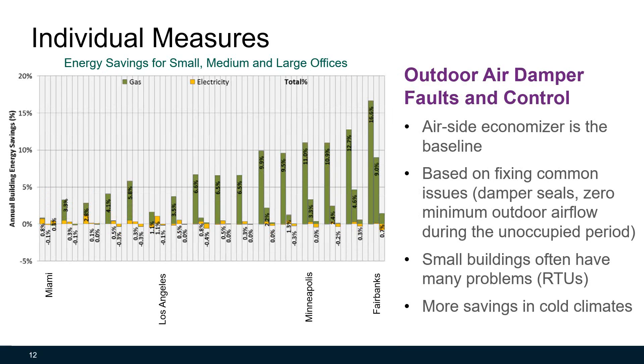In the outdoor air damper faults and control strategy, the air-side economizer is the baseline. This strategy is basically fixing issues with the air-side economizer, such as leaky dampers. Small buildings often benefit from this measure because rooftop units are often not well maintained.